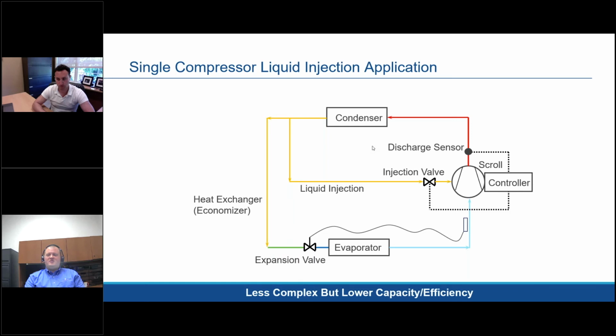Like I said, it's a simple system, so a lot of times that's a quick and easy system to get out in the market, but you don't get that extra capacity with liquid injection because you're not bringing that vapor back to the compressor to get compressed and move more mass flow out to the condenser at that point. So you're losing capacity, you're a little bit less efficient as well, but it's a quick, simple approach to it as well.